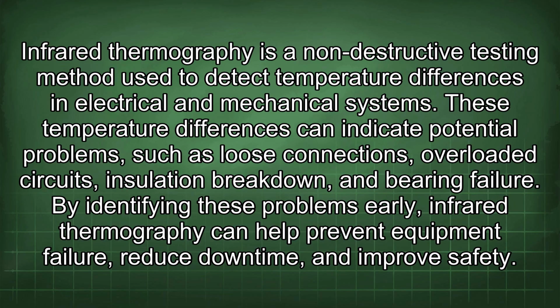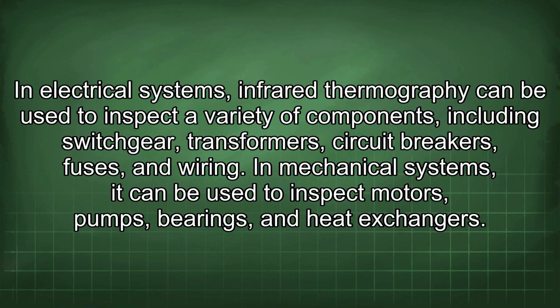Infrared thermography is a non-destructive testing method used to detect temperature differences in electrical and mechanical systems. These temperature differences can indicate potential problems, such as loose connections, overloaded circuits, insulation breakdown, and bearing failure. By identifying these problems early, infrared thermography can help prevent equipment failure, reduce downtime, and improve safety. In electrical systems, it can be used to inspect switchgear, transformers, circuit breakers, fuses, and wiring. In mechanical systems, it can be used to inspect motors, pumps, bearings, and heat exchangers.